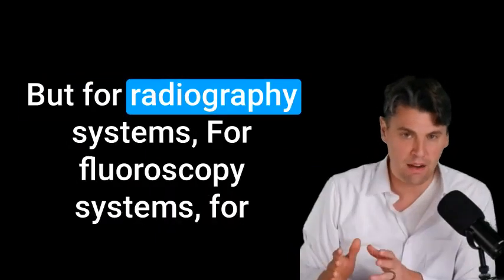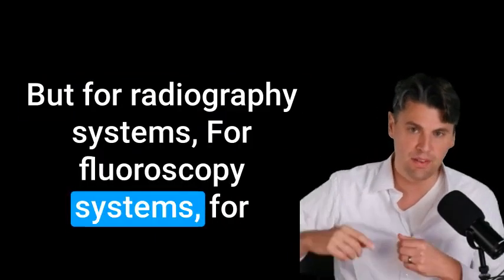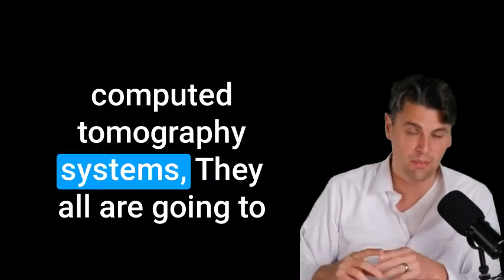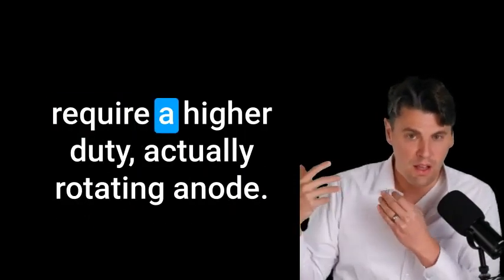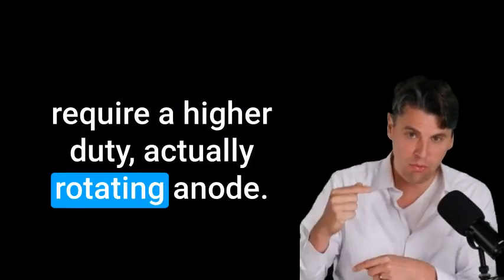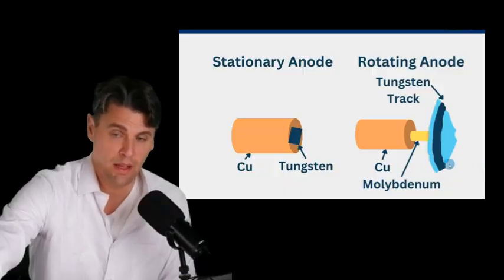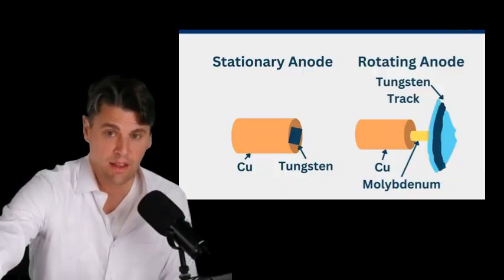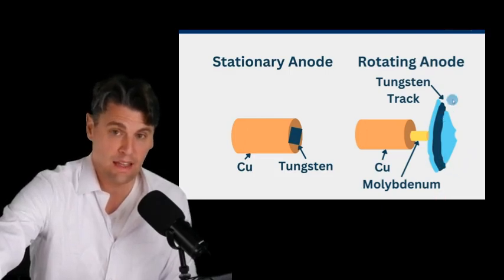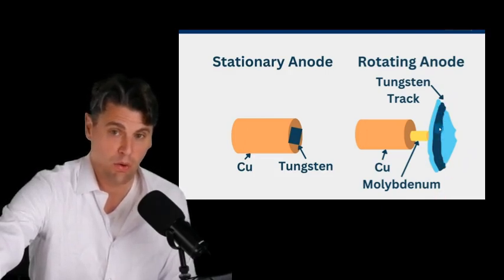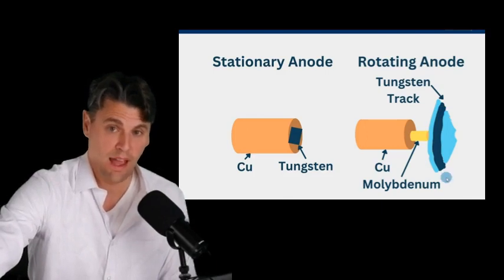But for radiography systems, fluoroscopy systems, for computed tomography systems, they all are going to require a higher duty, actually rotating anode. The electrons will come in, they will hit the anode, and then the x-rays will come out down here. So we can think about it, the heat can get distributed along this whole track for the actual anode.